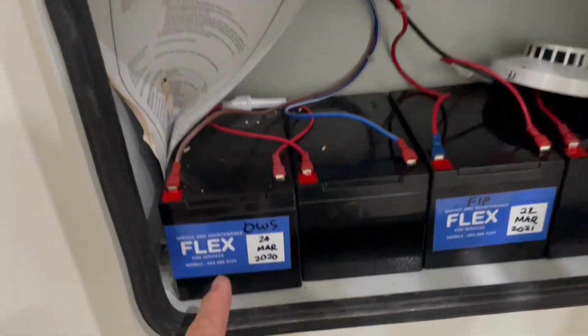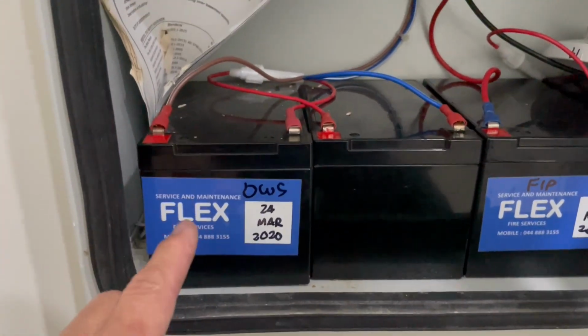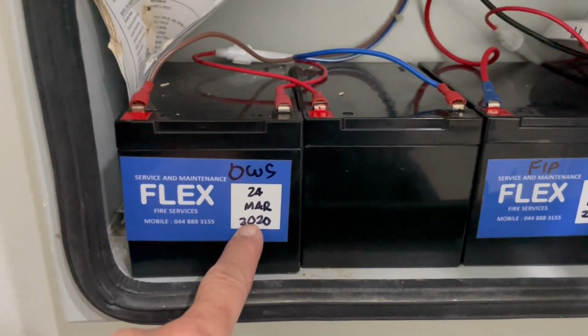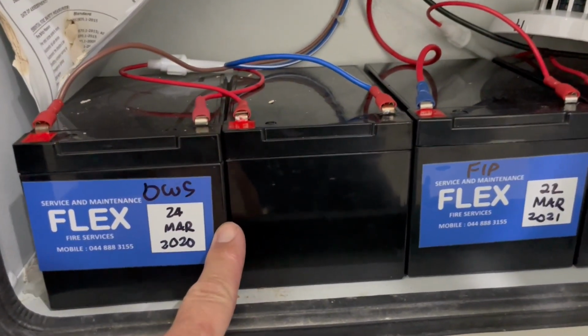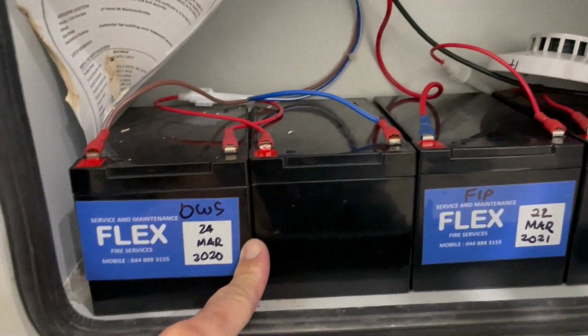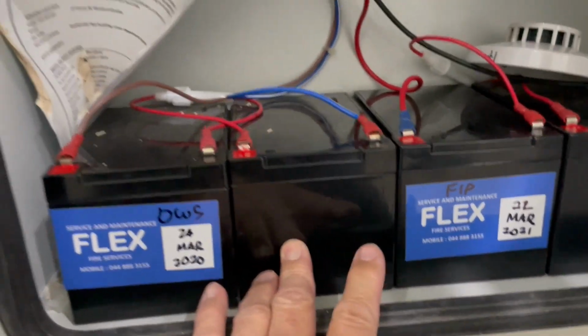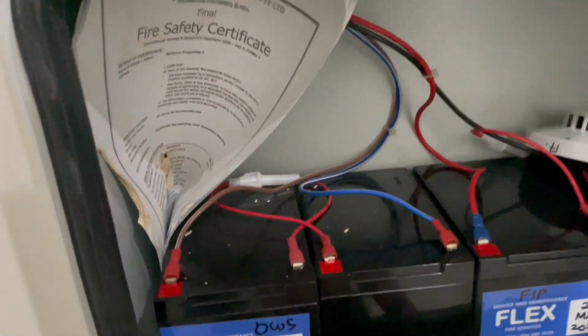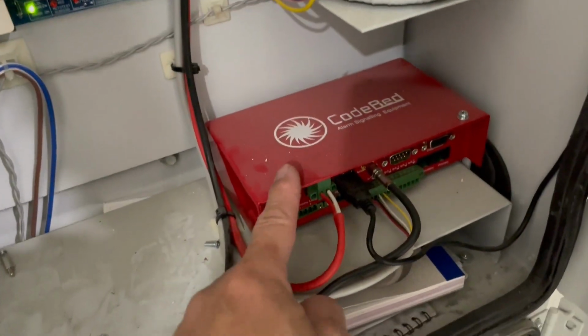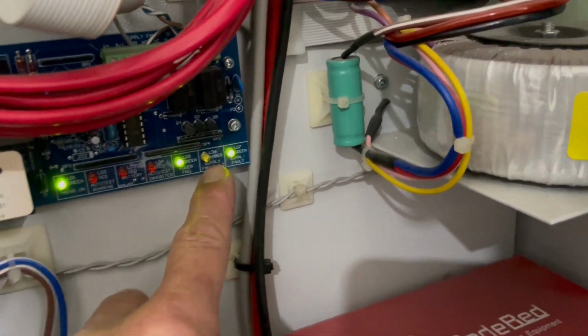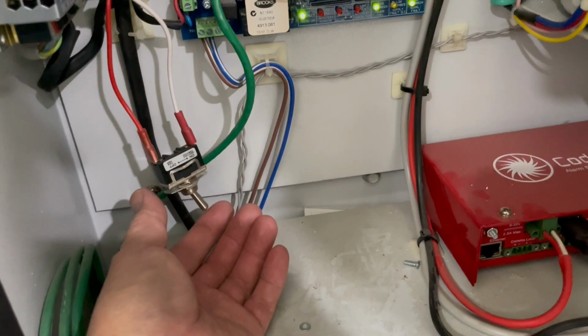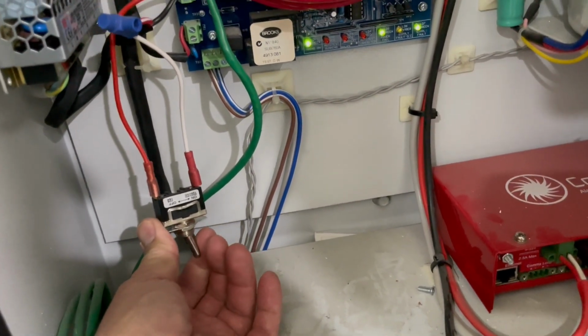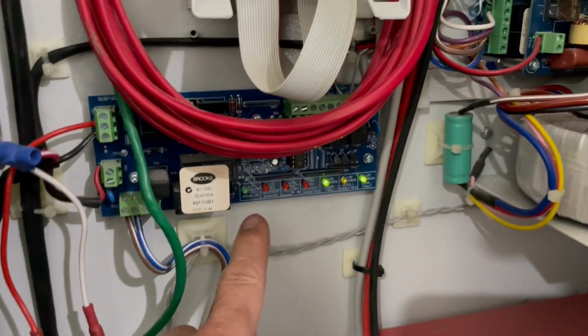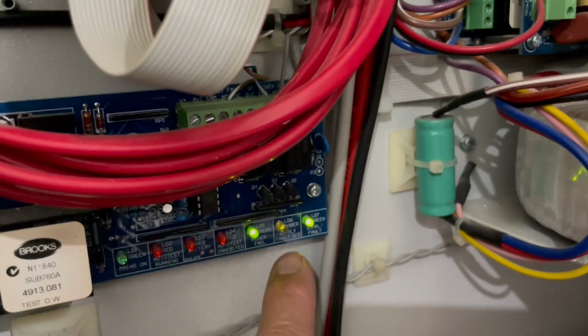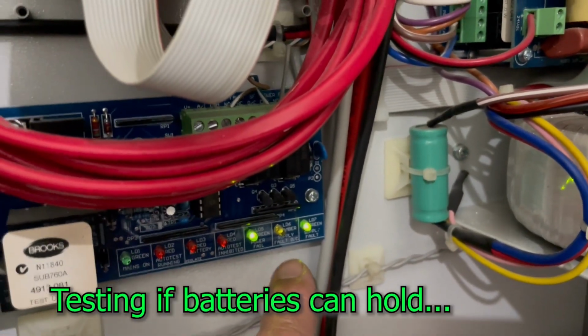Okay, what will happen next is, like I mentioned earlier, I'm going to replace this battery. It's already more than 2 years old. That's the one that's providing us an intermittent fault, and I hope that will clear it. For the meantime, I'm going to wait for another call from Code Red that there is a fault that came up there. That's a power supply fault. Okay, let's try an experiment. Let's switch off the power for the occupant warning system. Okay, power's gone. And let's see if that power supply fault will come up.